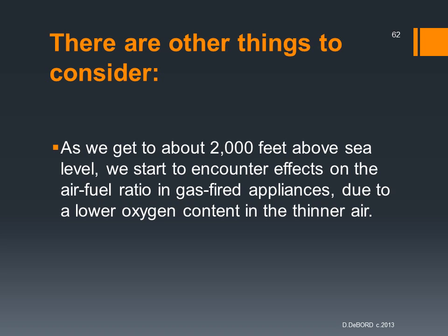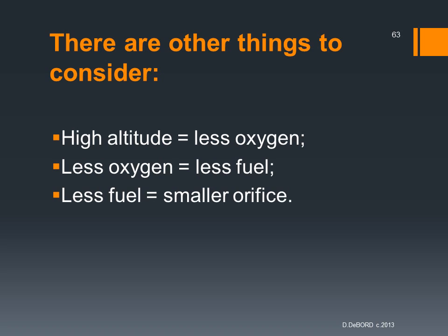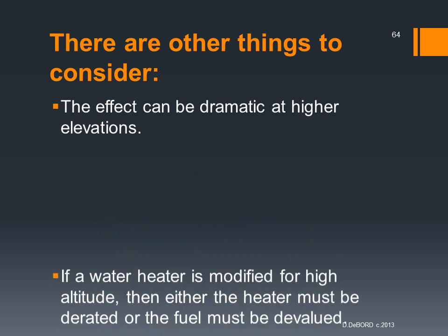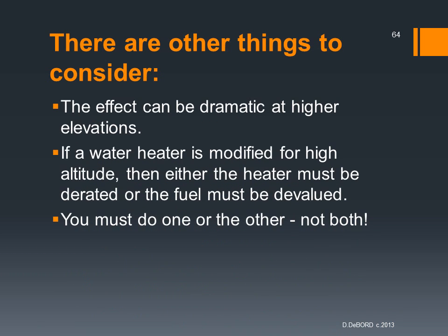Some other things to consider: as we get to about 2,000 feet above sea level, we start to encounter effects on the air-fuel ratio in gas-fired appliances. That's because we have a lower oxygen content as the air gets thinner. High altitude means less oxygen, and that means that we need less fuel. And less fuel means a smaller orifice on the boiler or the gas-fired appliance. This effect can be very dramatic at higher elevations, and if a water heater is modified for high altitude, we need to make sure that it's derated or the fuel must be devalued. If you do one but not the other, you can do one or the other but not both.